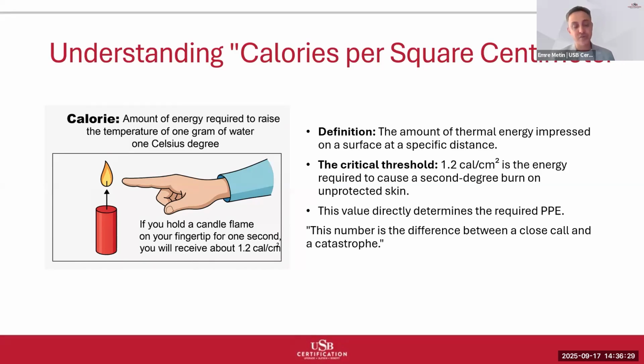The critical threshold we work with is 1.2 calories per square centimeter. This represents the incident energy level that will cause a second-degree burn on unprotected human skin. This isn't theoretical. It is based on medical research into burn injury mechanisms. To put this in perspective, the illustration shows that if you hold a candle flame against your fingertip for 1 second, you'll receive approximately 1.2 calories per square centimeter of energy.